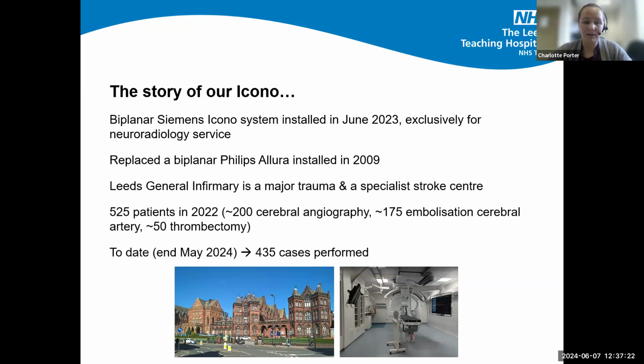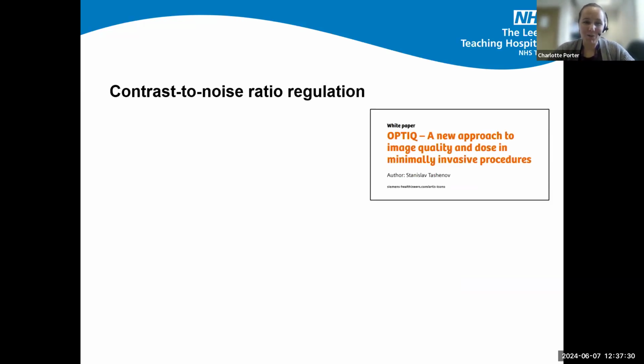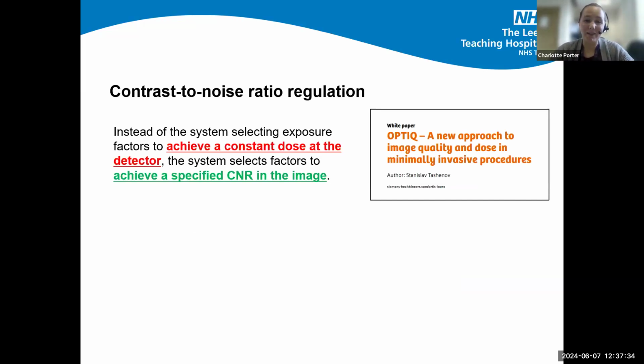And to date, or to the 31st of May, we've done 435 cases on our new system. So obviously we know, that's why we're here, that this system does not work in the way that we are used to historically with our fluoroscopy systems. So it aims to achieve a specified contrast to noise ratio in the image. I'd highly recommend this white paper that Siemens have published if you're getting an Icono, because it does go through a bit of the detail on what they do.